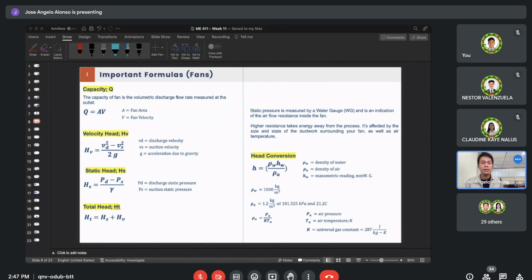When it comes to static head, the formula is the pressure at discharge or outlet minus the pressure at inlet, divided by the specific weight. What is specific weight? We won't use 9.81 kN per cubic meter here, nor will we use 62.4 pounds per cubic feet. The specific weight here will be the specific weight of our air, since our medium here is air and not water.